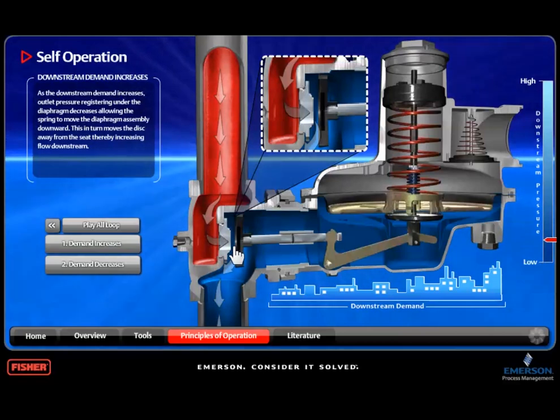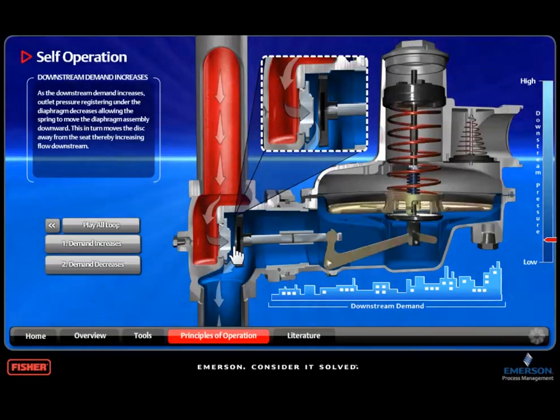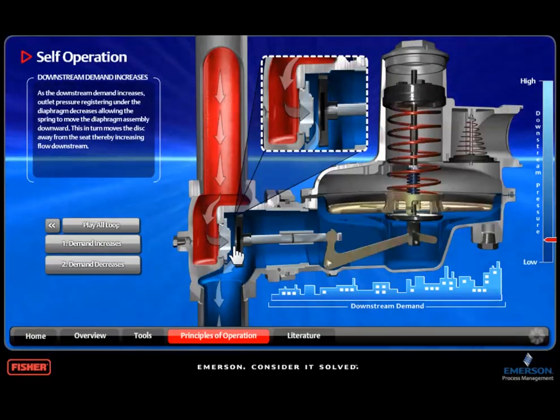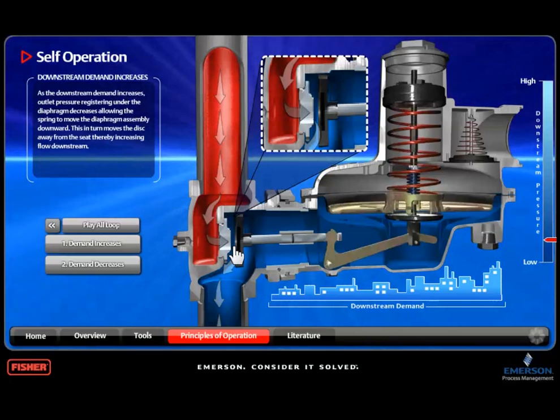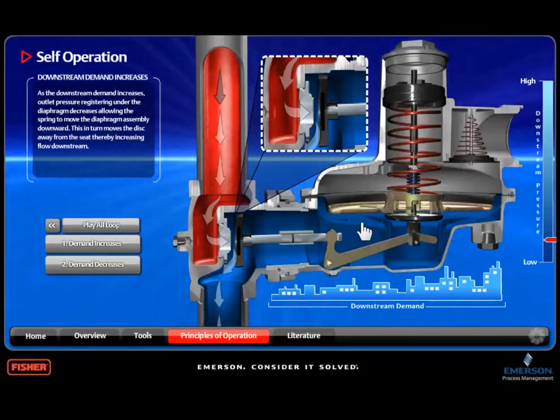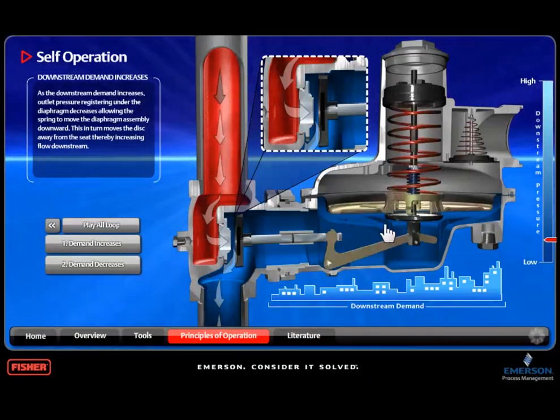The most important takeaway is that the only way the disc will move in any direction to restrict or allow more flow is if the diaphragm senses a change in outlet pressure.